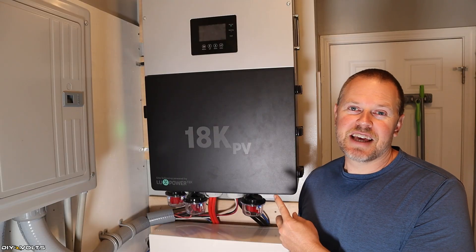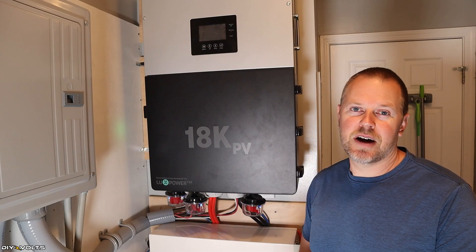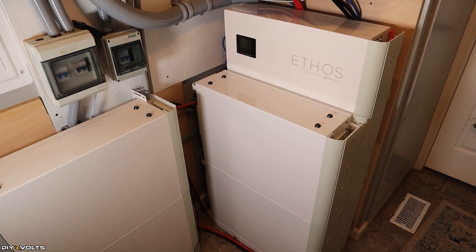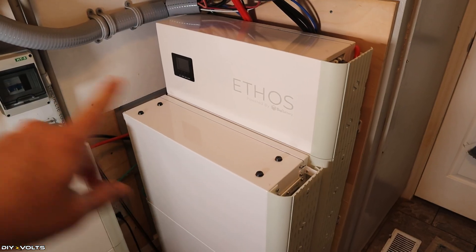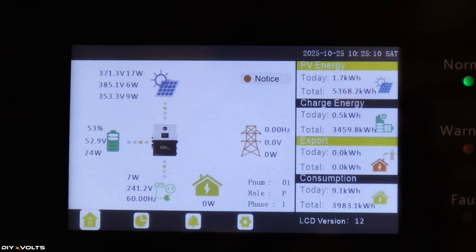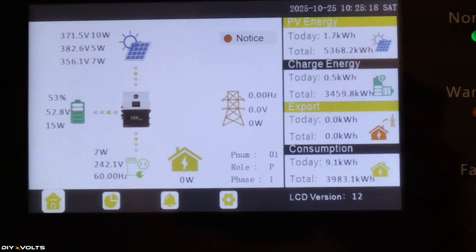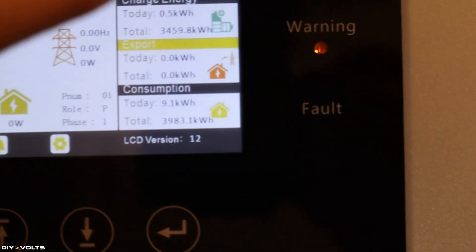When it comes to batteries, the EG4 18K can accept tons of different models and styles, but I use the Big Battery Ethos. Let me show you my 30 kilowatt hours of battery storage. I have six modules of the Big Battery Ethos for a total of 30 kilowatt hours. These little boxes weigh 100 pounds each, they're 5 kilowatts each, and you just stack them on top of each other. They all wire together with their communications cable and battery cables, which go to the control box that talks to the EG4 18K inverter. You can see on the display that the state of charge is correct, but the watt values on the screen are still mixed up.